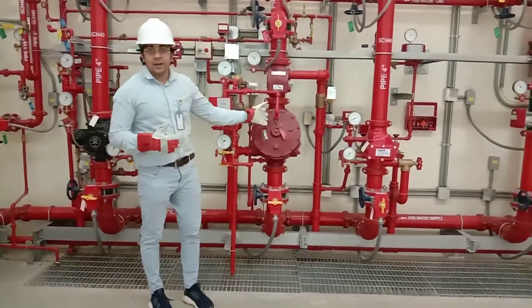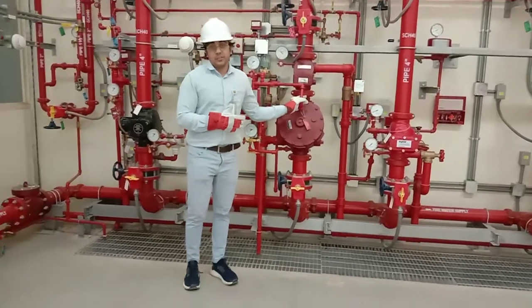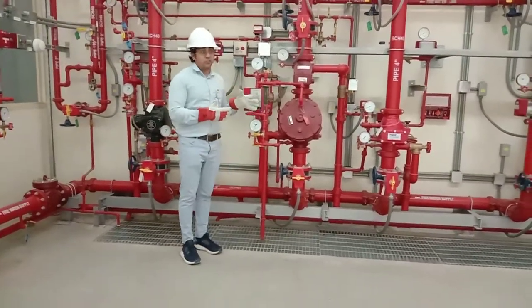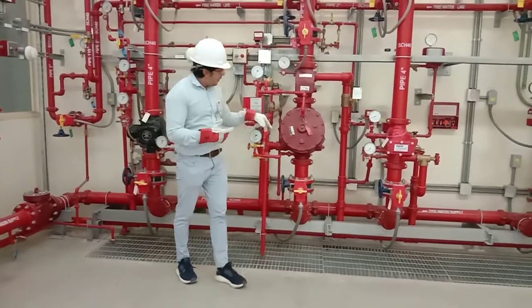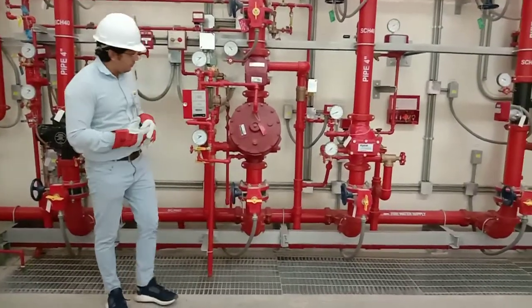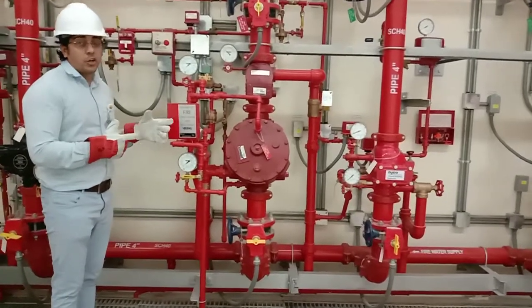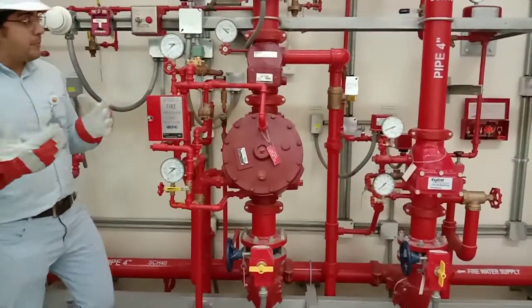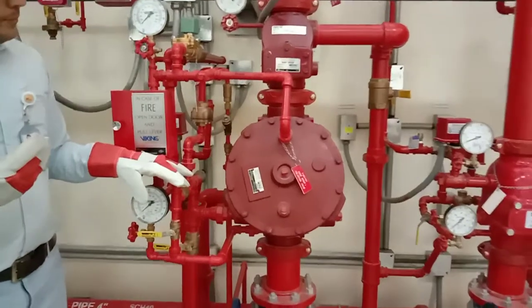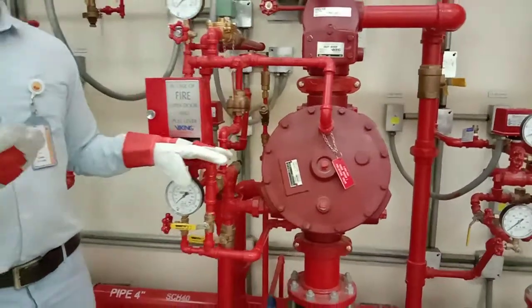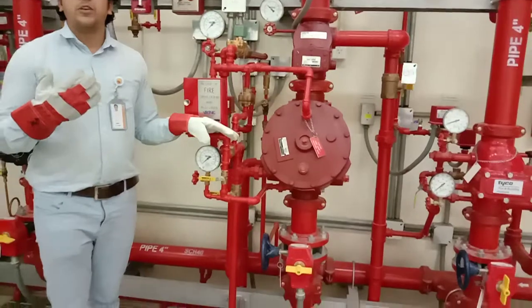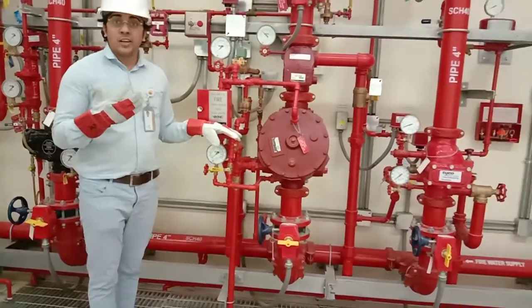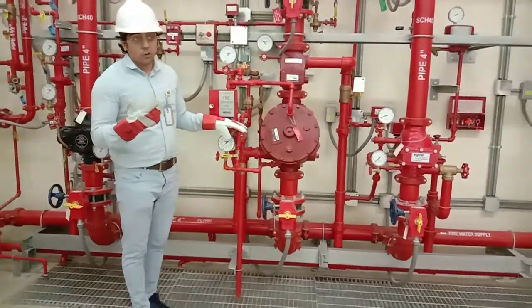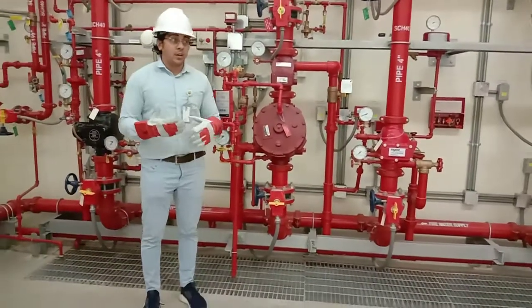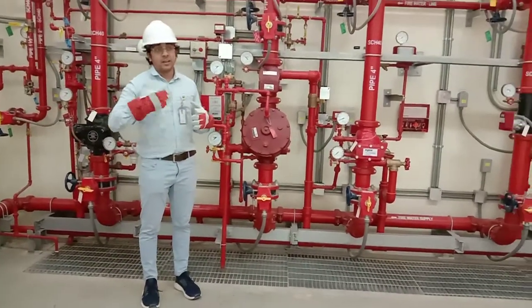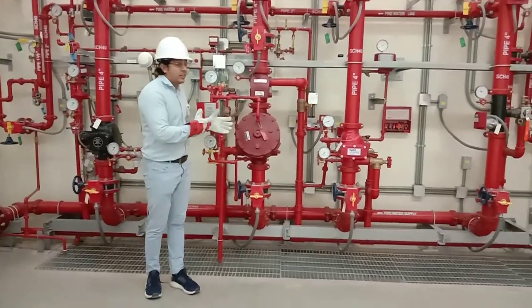The last one we have in the series is the pre-action system. The one we have at the JIC Fire Safety Training Center is a deluge valve, model F1, double interlock pre-action system. Now, normally with the pre-action system, we have three different types of system. We have the non-interlock system, the single interlock system, and the double interlock system. Before going into detail of those interlocks, I want to highlight where we use this kind of system, right?